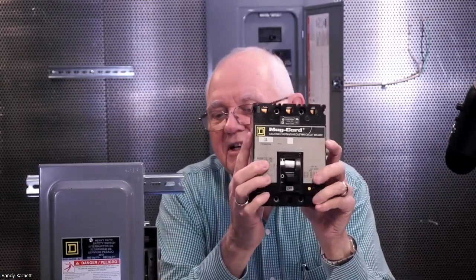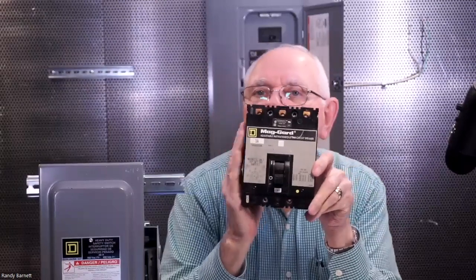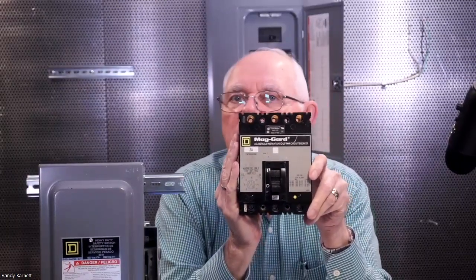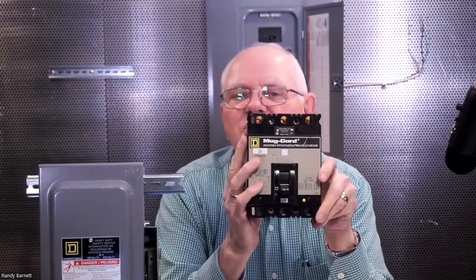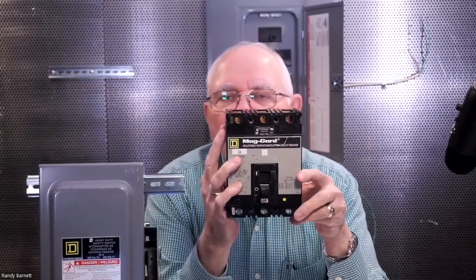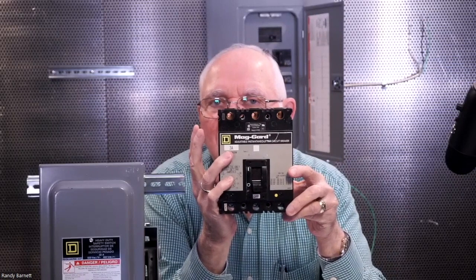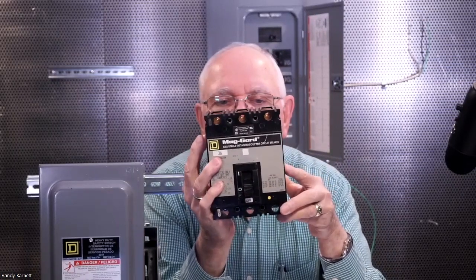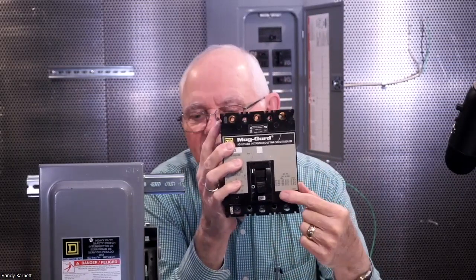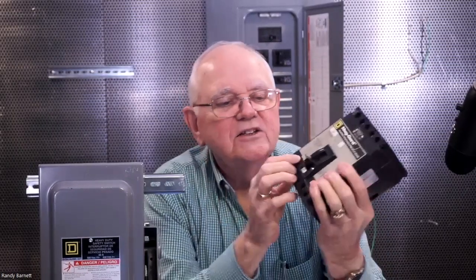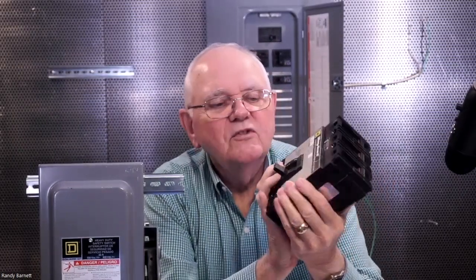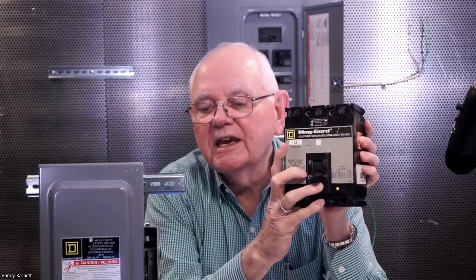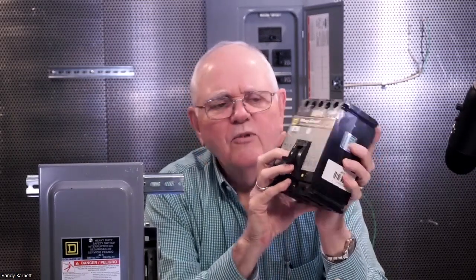The magnetic gives me short circuit and ground fault protection. The thermal portion of the breaker gives me overload protection. No overload protection on this breaker. So by definition in Article 240, this becomes a motor circuit protector. It's actually an informational note in Article 240. If it provides instantaneous trips only, magnetic trips only, and if it is adjustable, and I can adjust the magnetic trips, actually it's right here, it gives me a value. It says 3 amps up here. So you'd say, well, it's a 3 amp breaker.